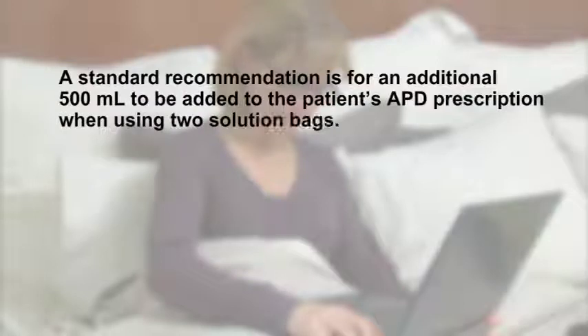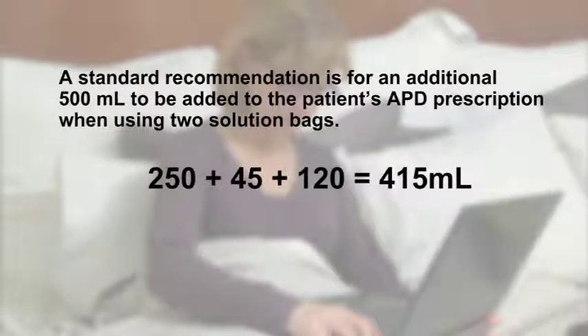A standard recommendation is for an additional 500 milliliters to be added to the patient's APD prescription when using 2 solution bags. In this example case, 250 milliliters would be needed to prime the heater bag and complete the integrity test, plus 45 milliliters to prime the patient line, plus 120 milliliters to prime the supply line, equaling 415 milliliters.